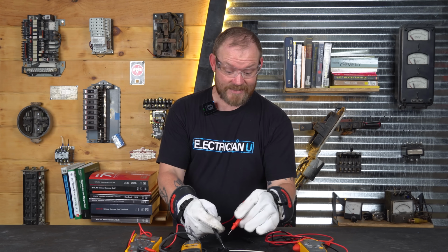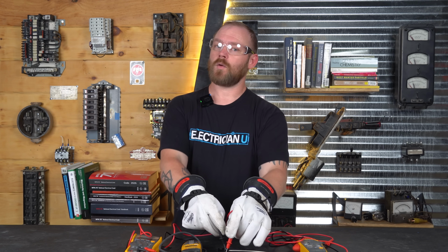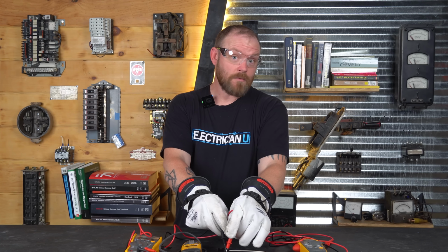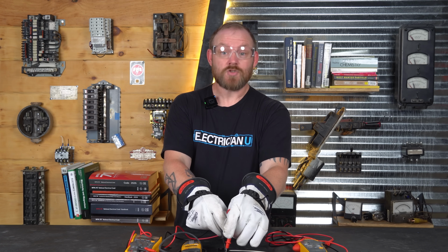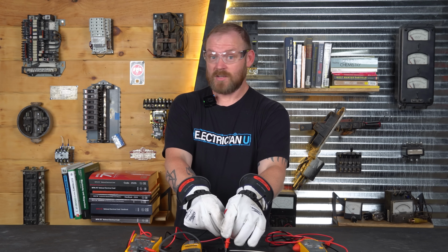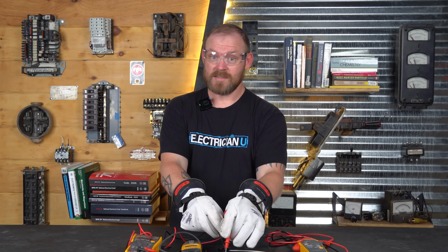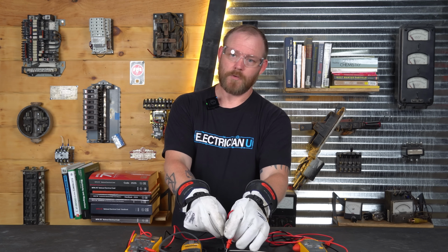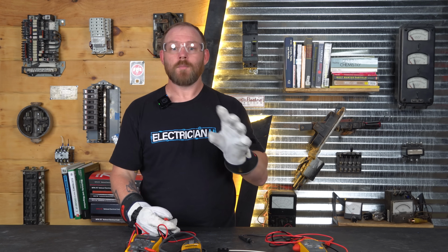So the low Z mode lets us know, oh, this isn't a voltage drop. You know, if I tested this and I actually got still like 62 volts or something on low Z mode, I would be like, whoa, okay, I just have a voltage drop. There's actually real power behind this because it is driving current through this low impedance of the meter. So this might be able to actually drive a load. But when it says 0 on low Z mode, you know, oh, this is just a ghost voltage. There's something being induced on a conductor or capacitively coupled to make a voltage present.